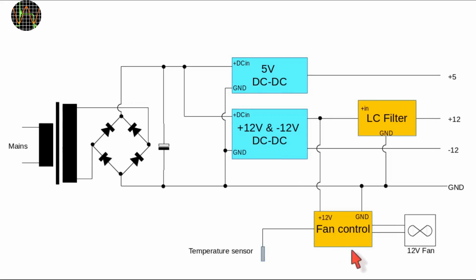The fan controller hangs off the plus 12 rail because, unfortunately, it isn't designed to survive the higher voltage of the DC behind the rectifier. The DC to DC converter can handle the additional current easily, but I was a little concerned about the noise added on the plus 12 volt line by the pulse width modulation of the speed control. For that reason, I added an additional LC filter into the plus 12 connection to the main board.